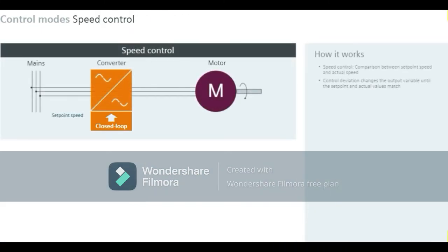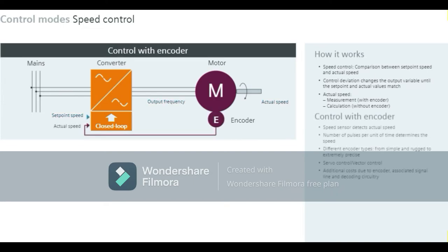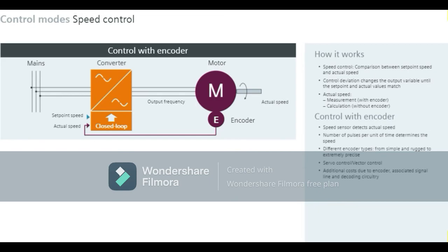During speed control, the set point speed is compared to the actual speed. The control deviation changes the output frequency until the set point and actual values match. The actual speed can be recorded using a speed sensor; the number of pulses per unit of time represents the speed. Different encoder types are available, from simple and rugged to extremely precise. Depending on the internal control structure, this is referred to as either servo control or vector control. However, the encoder, associated signal line, and decoding circuitry all increase costs.